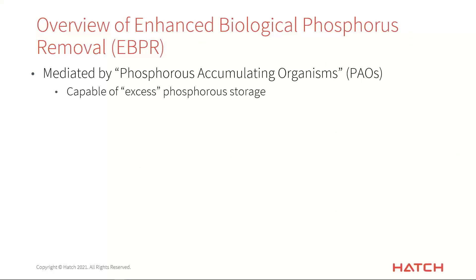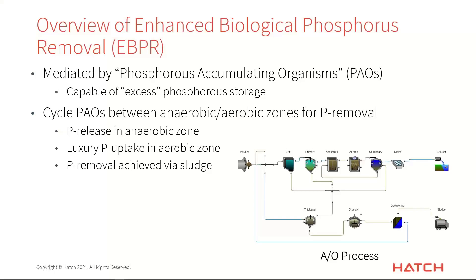We do this in the model and in actual wastewater treatment plants by growing PAOs — phosphorus accumulating organisms — that are capable of excess phosphorus storage. This is done in two steps: first, going into an anaerobic zone along with enough substrate, where it releases phosphorus while storing COD as PHA. In that anaerobic zone, you will see a release of phosphorus — a higher soluble ortho-P concentration. Then it moves on to an aerobic zone where it uptakes the phosphorus while growing on the stored COD.